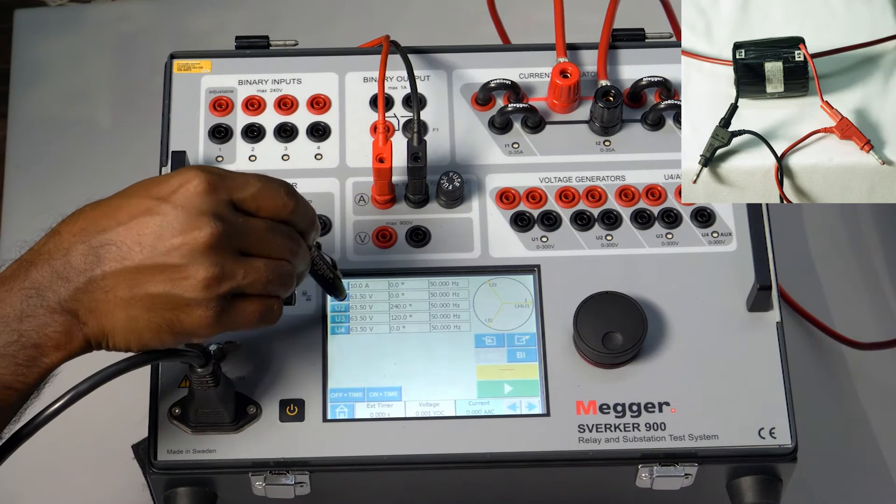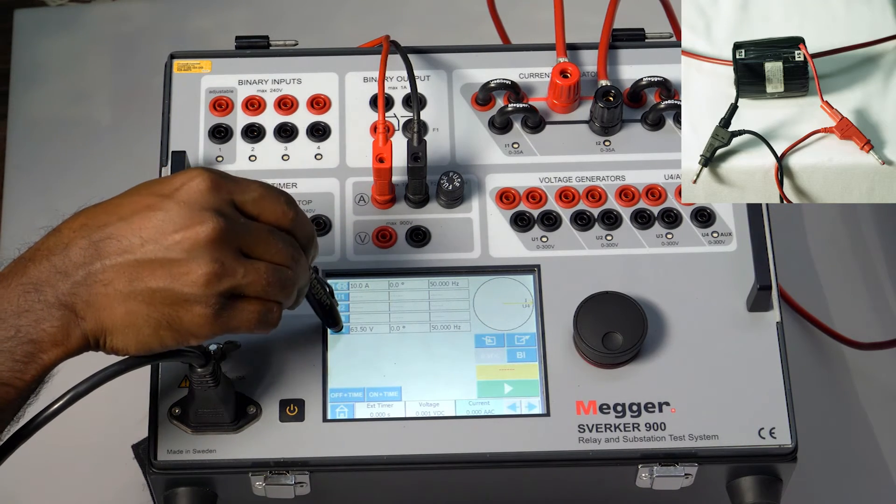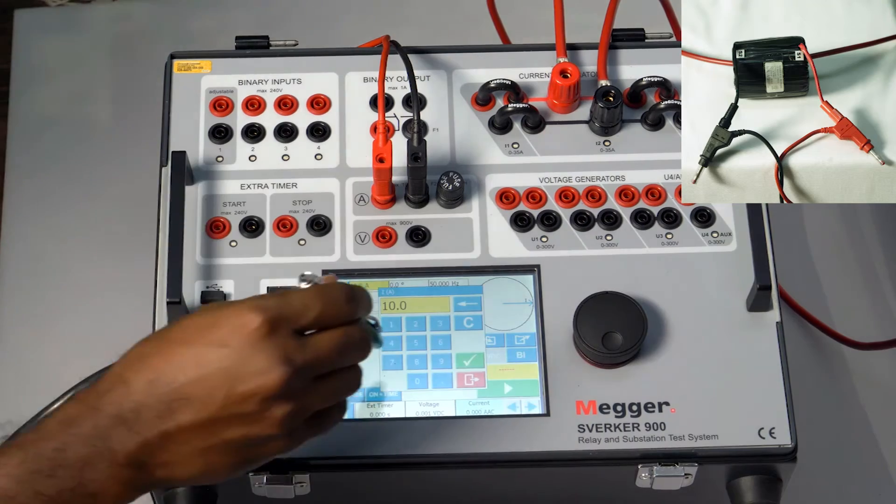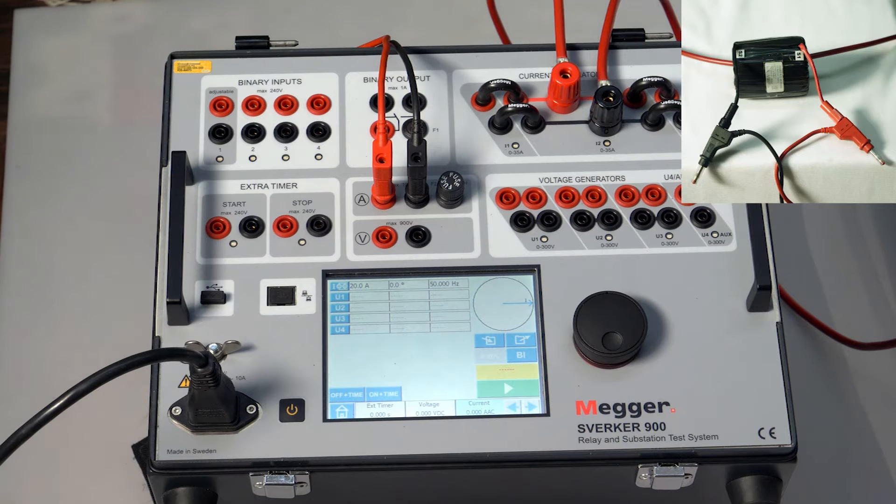I'm not going to use the voltage, so let me switch it off. I'm going to inject in multiples of 20. So let me inject 20, 40, 60, 80, and 100 amps. Each time I will inject for 5 seconds till the value is stabilized.